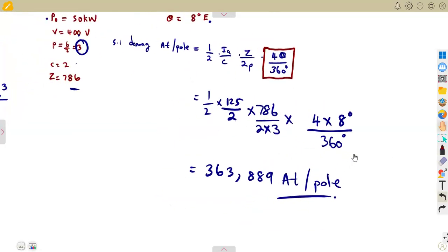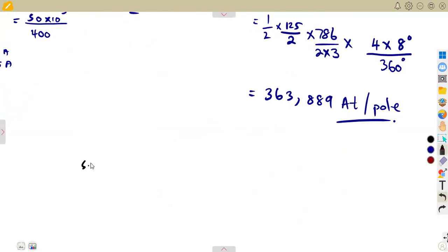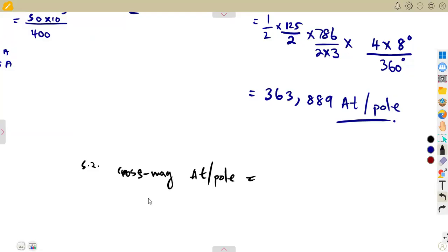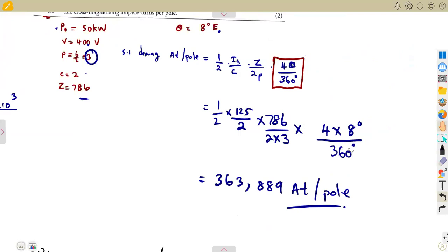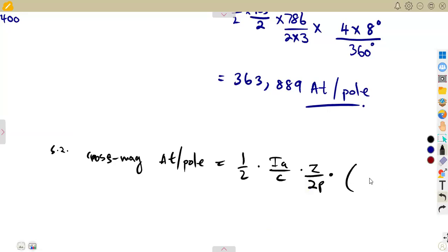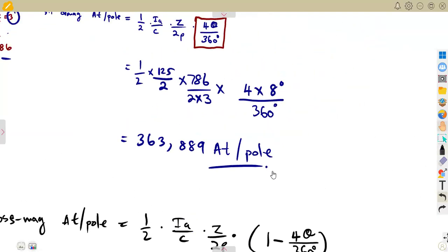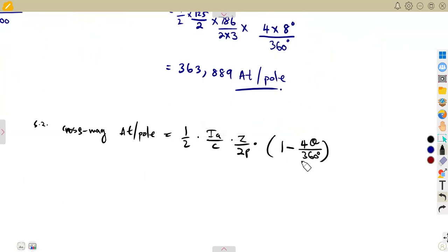For part 5.2, the cross-magnetizing ampere-turns per pole: the base part of the formula does not change — it remains one-half times the armature current over C, times Z over 2P. This time, however, we extend it by multiplying by the factor one minus four-theta over 360 degrees.